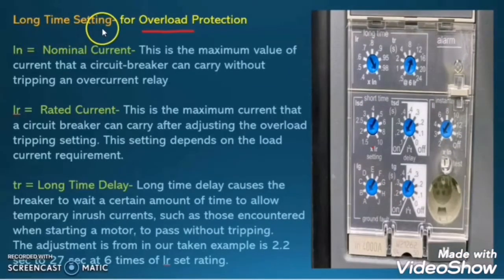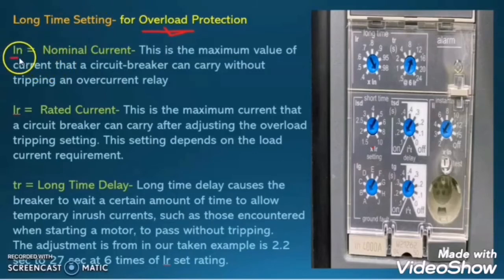The long time setting gives protection against overload. But before understanding long time setting, we need to understand what is nominal current and what is rated current. Here in our example, IN is equal to 4000A. The IN is the nominal current — this is the maximum value of current that the circuit breaker can carry without tripping an overcurrent relay, meaning this breaker can carry a maximum of 4000A.